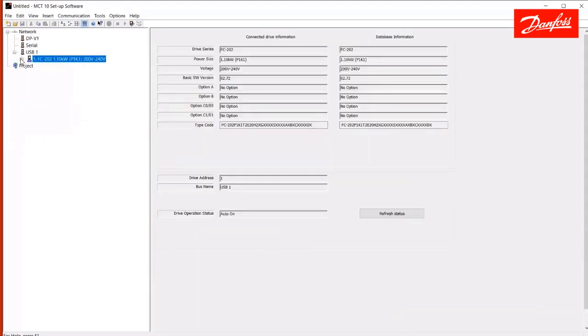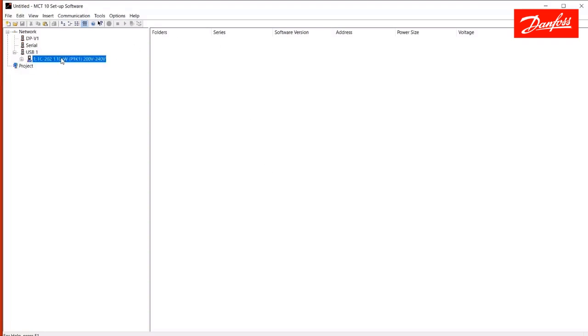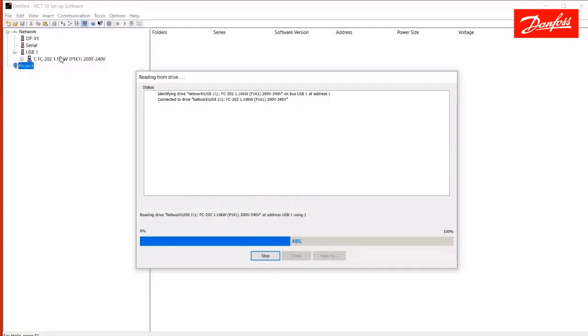So I'm going to move on to the project side here. The project side is where you need to pull a drive into to allow you to save it. So the easiest way to do that, for example, you're in a factory and you want to back up the drives in that factory to a project. You'll approach the drive of interest, plug into the USB, and it will appear on the USB side like shown here. And I will drag and drop that drive into the project. This will take a few seconds here. When it finishes up, we'll see that this drive has been copied from the live network side over to the static offline project side.